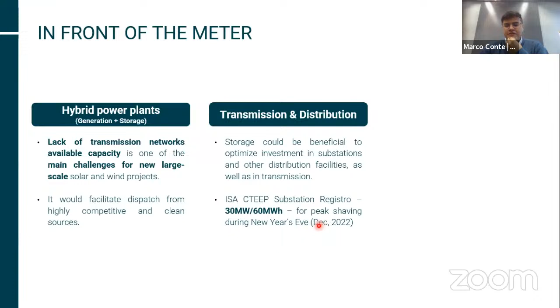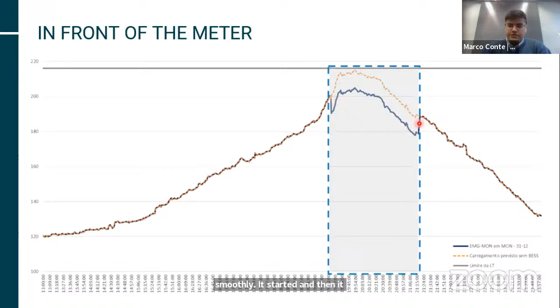I brought here what would be the load profile that ISA-CTEEP was forecasting. The yellow dashed line is the forecast, the gray line is the total transmission capacity the grid could possibly offer, and here we see the discharge of this BESS, this battery storage system. With the implementation of this project, there was no blackout, because the main risk was of a blackout due to overcharging. We can see the operation went smoothly: it started and then ended its discharge.